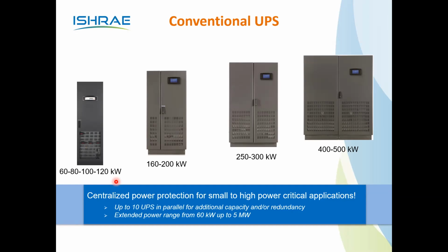What is the input power factor? For most of the technology, the input power factor is unity. It's a better power factor, no doubt about it. But when it comes to the output power factor, that is where the challenge is. Some technologies are 0.8, some are 0.9, and some are unity. How is the customer going to benefit? If the output power factor is designed for 0.8, 100 kVA can support only 80 kilowatt load. If it is designed for 0.9, it can support a 90 kilowatt load. Designed for 1, it is 100 kilowatt. It's 100% power, 100% value for money.